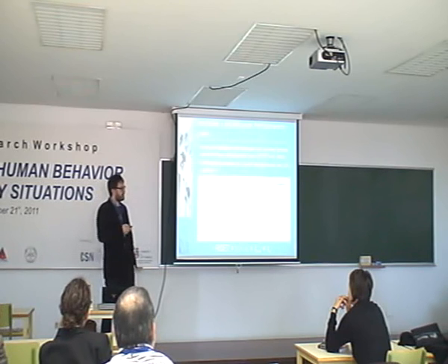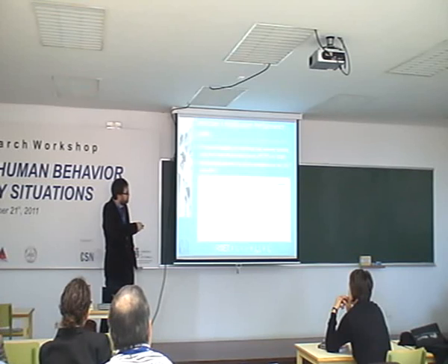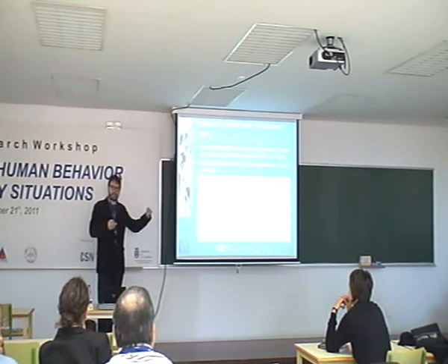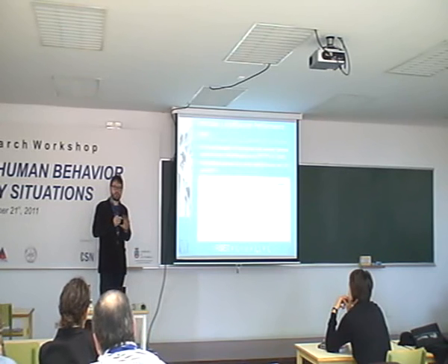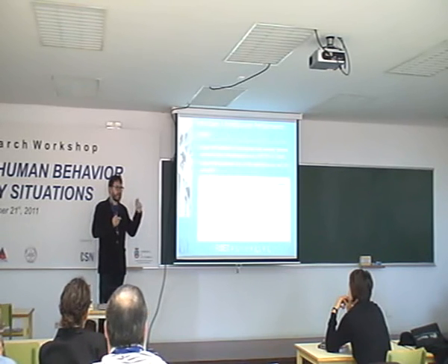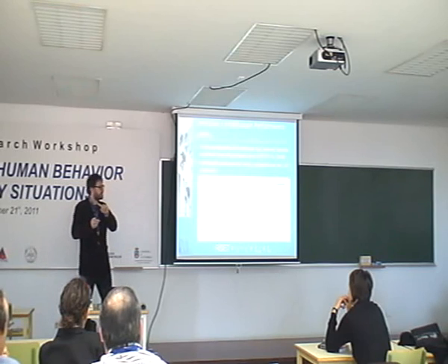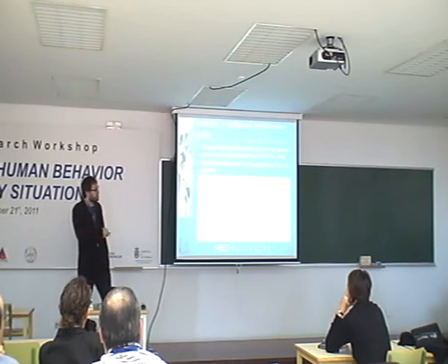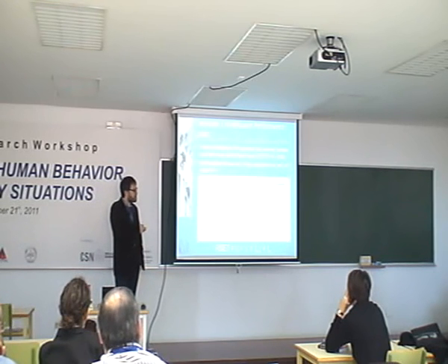Now, the original assumptions regarding detection and notification are broadly appropriate in the first case, where an alarm is detected, it's complete coverage, a complete detection system, is detected quickly, and then a signal is automatically sent and a general alarm is immediately distributed. So in that case, the manufacturer's assumptions may broadly be accepted.